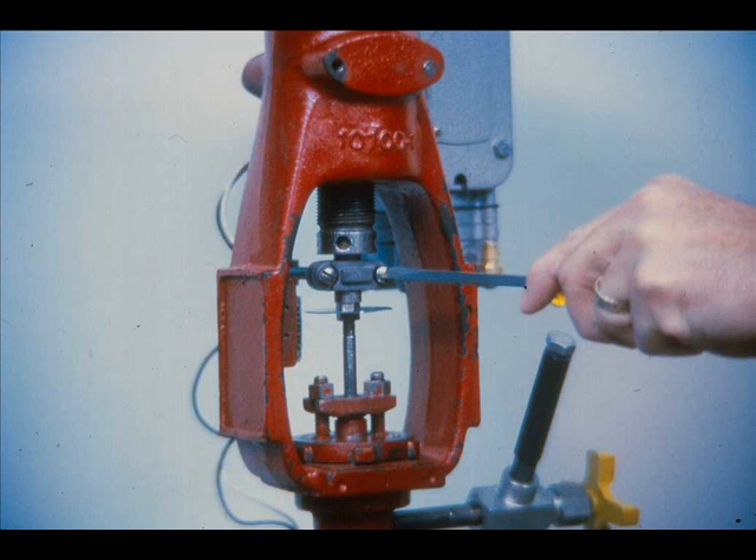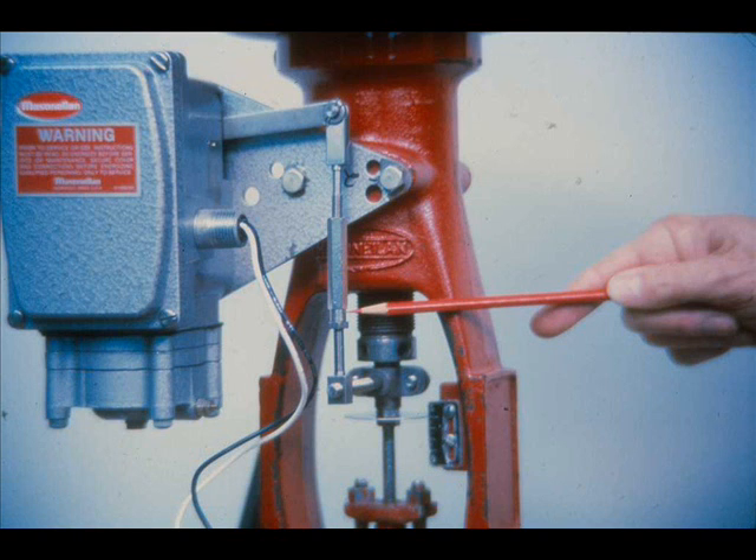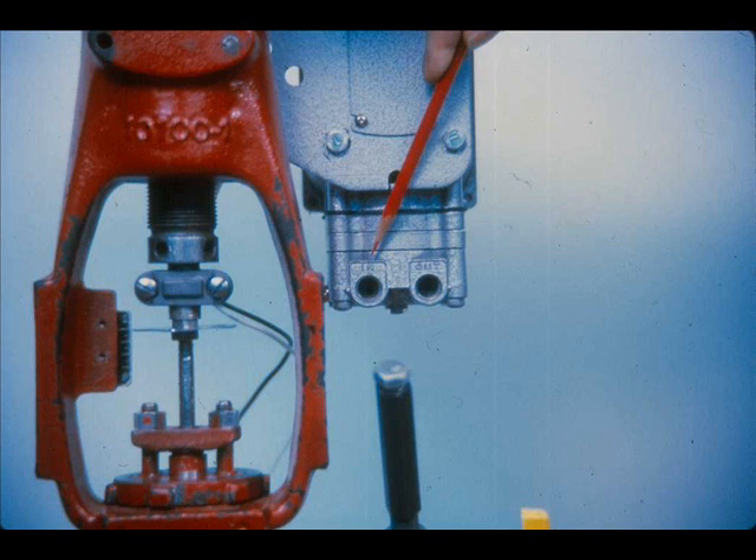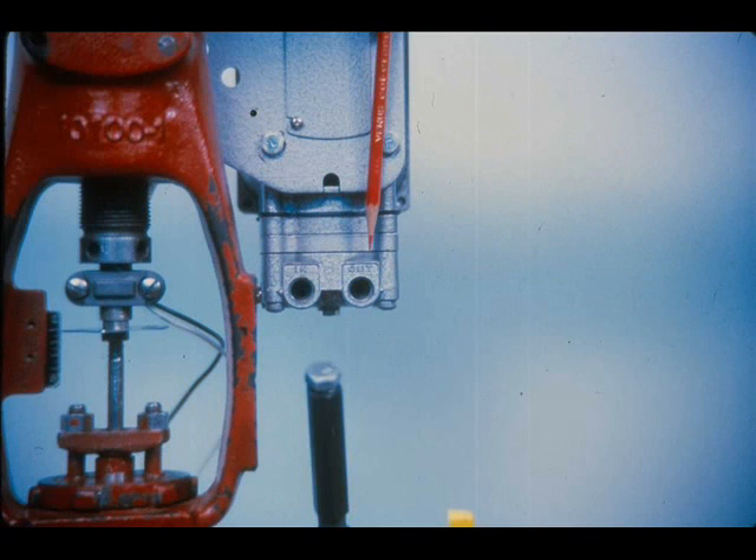After the positioner has been mounted, attach the take-off clamp to the actuator stem at a point which permits full actuator stem travel. The turnbuckle is installed in a vertical position between the stem clamp and the back lever clevis. The lower end of the turnbuckle hex has been machined round to identify the right-hand thread which engages the turnbuckle screw. Larger actuators require a longer turnbuckle and stem clamp rod. Connect a regulated air supply to the quarter-inch connection on the relay marked IN. Connect the valve actuator to the quarter-inch connection on the relay marked Out.